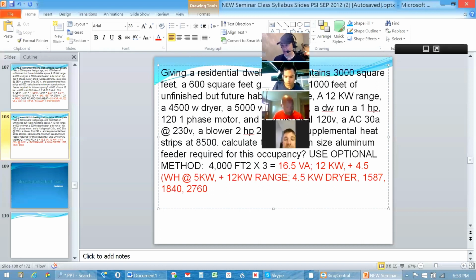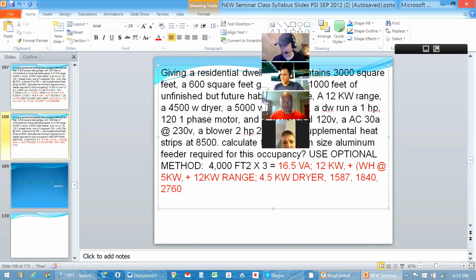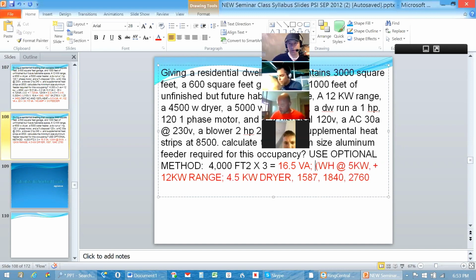So I'm going to add the 16.5 for the lights and plugs. I'm adding the 4.5 and the 12. Plus the 5, plus the, did I count that 4.5 twice? I did, didn't I? I already had the dryer listed down there, so I'm not going to include it twice. So I got the range. Let me make sure. So 16.5 plus the 12 for the range, plus the 4.5 for the water heater. Excuse me, the dryer, which I've got a little further down there. I don't need to go up there either. So the water heater 4.5.